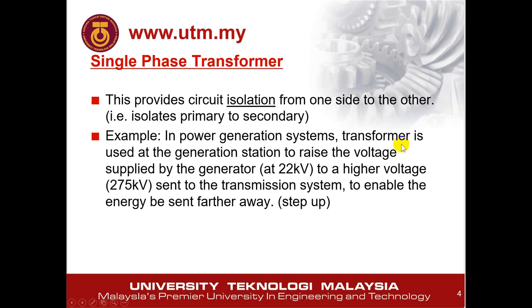In an electrical power generation system, a transformer is used at the generation station to raise the voltage from 22 kV to a higher voltage, which is around 132 kV, 275 kV, or 500 kV. You can refer to chapter 3 on the theory of the three-phase system. Note that the power generation system in Malaysia uses a three-phase system, not a single-phase system. We increase the voltage to reduce the current, allowing power to be sent further away because we reduce power loss due to lower current.